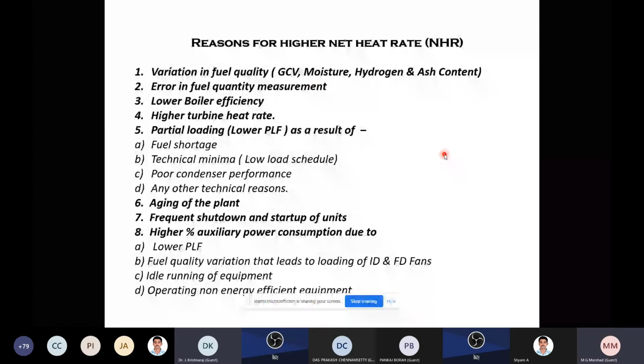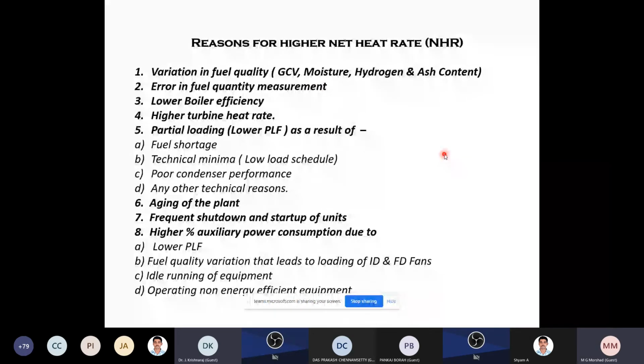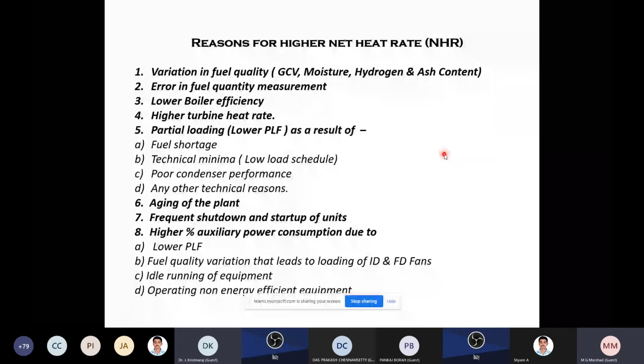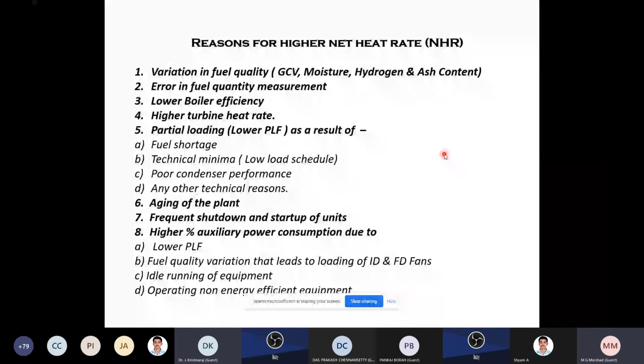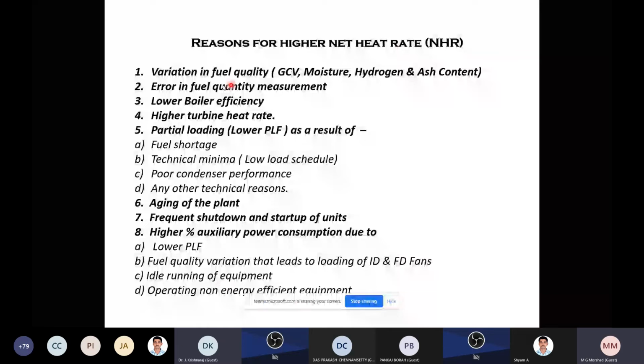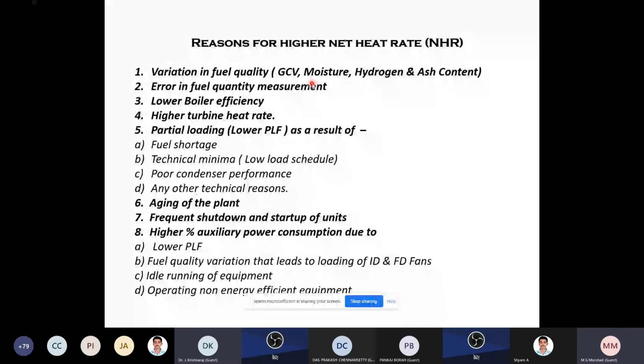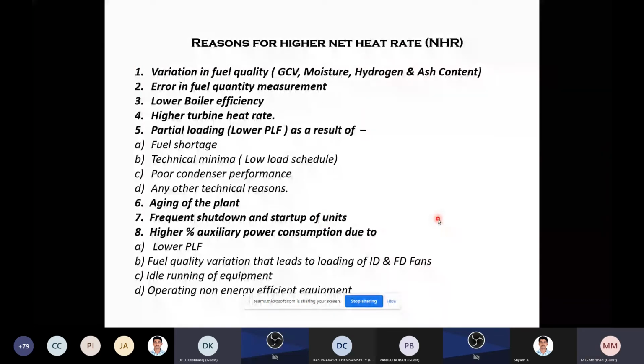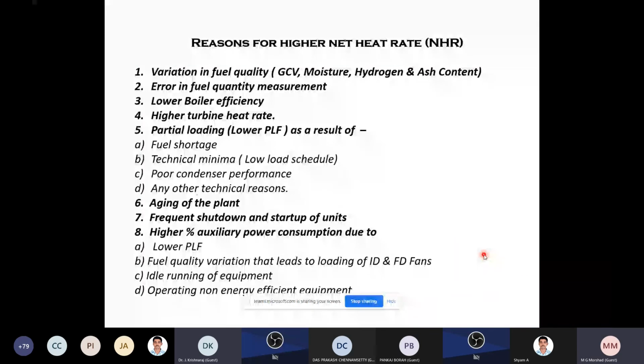See, sometimes during the energy audit, they don't find any reasons to write for the higher heat rate. So these are all the causes that can be behind a higher net heat rate. The energy auditor, internal or external, can take this idea and give their justification for the net heat rate. So this is also a very important thing. This is what I did during my energy audit in my plant.